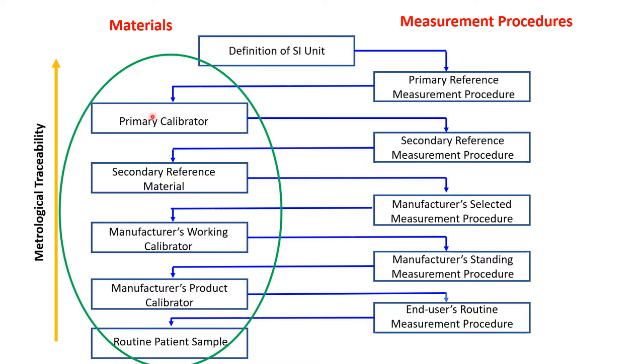I want to focus on the materials used in the standardization process. The various reference materials used in the transfer protocols are key components in transferring the accuracy of the primary reference measurement procedure to the end user's routine measurement procedures. Reference materials are used to establish trueness of measurement procedures through calibration or to assess the trueness of the calibration of a measurement procedure. Uses may include the calibration of a measurement system, assessment of a measurement procedure, assigning values to other materials, and quality control. A reference material can only be used for a single purpose in a given measurement process.